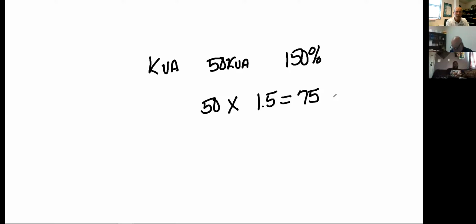Here's the question. Read it closely. How much in kVA will a 50 kVA transformer do in short-term overload? Here's my 50 kVA. It'll go to 150%. That translates to 75 kVA, not 75,000 kVA. Gotcha. Okay. Perfect. All right.